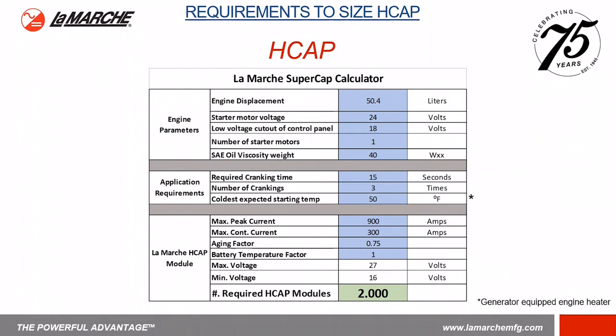In this particular case, we're using 50 degrees Fahrenheit because it's equipped with an engine generator heater. And then which module you're going to use. We have 2 different versions, the 600 and 900. And the maximum current, there's an aging factor, and then also the battery temperature factor. In this case, it'd be 1. There really isn't any because it's got a wide range of operating temperature from minus 40 to plus 65. And then also the min and max charging voltages. In this case, this particular requirement calls for only 2 HCAP modules.